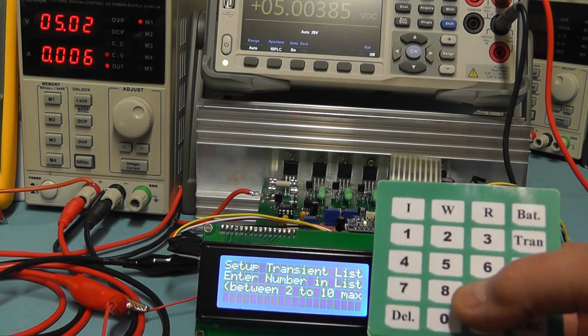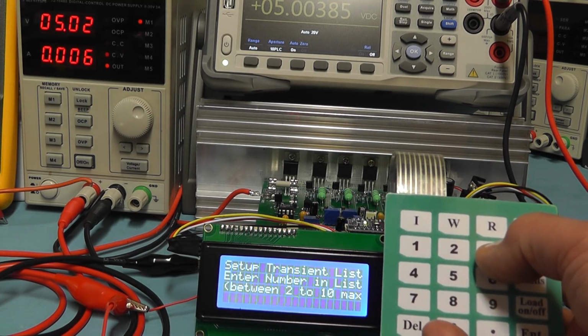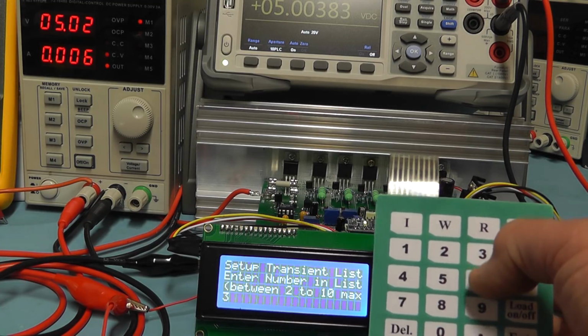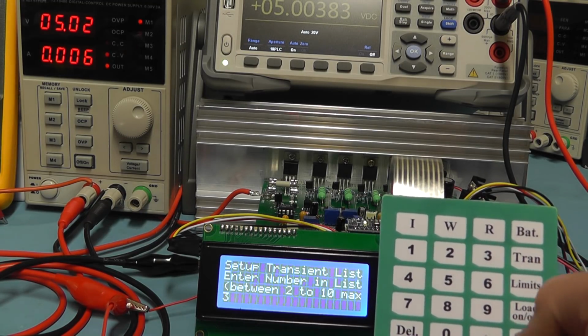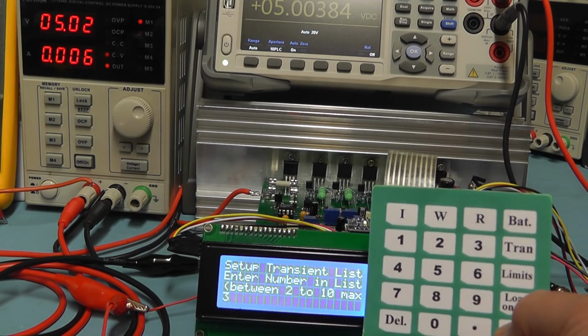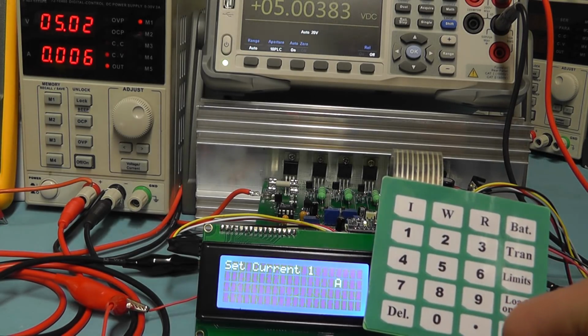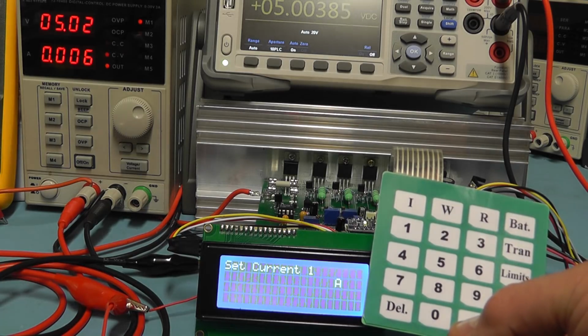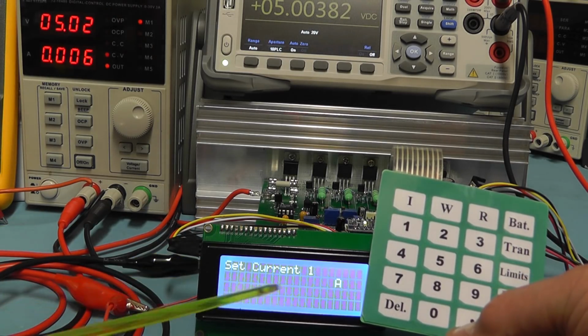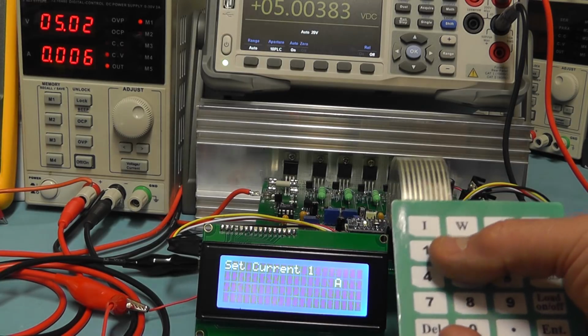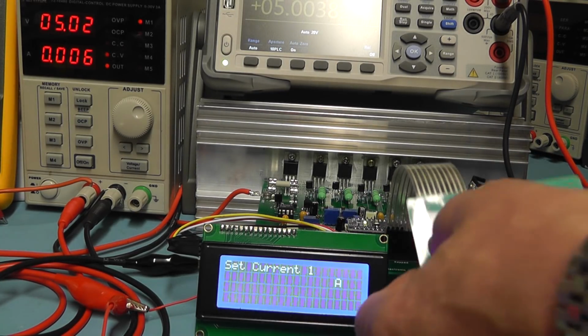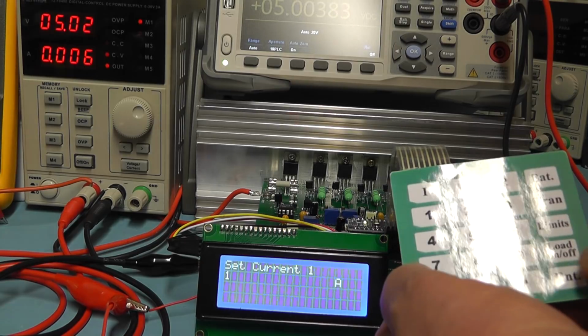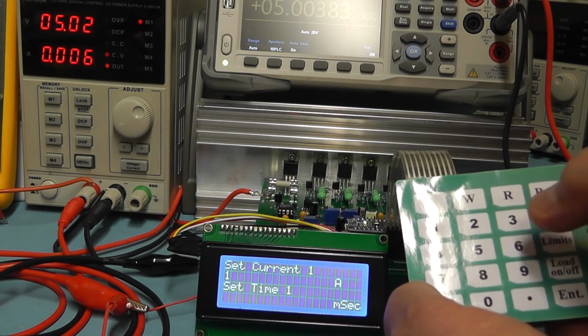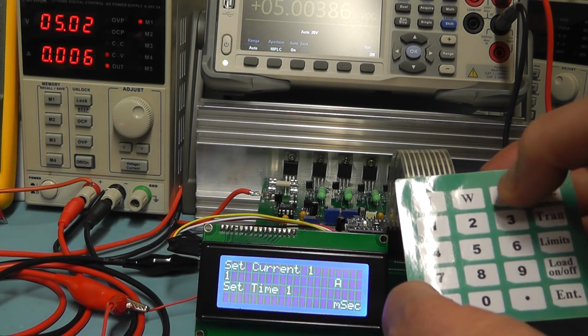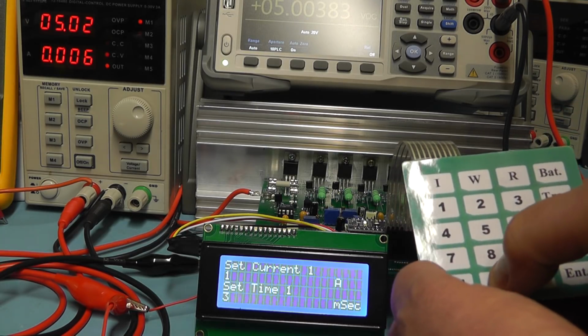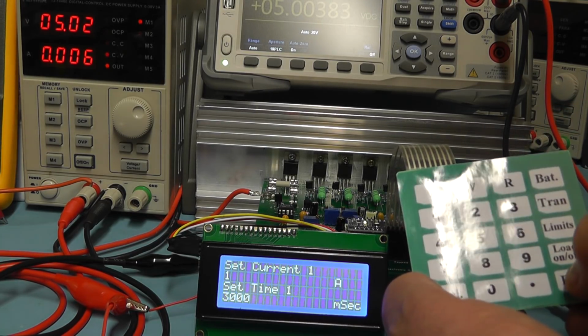So let me choose, just for this example, I want to say 3, so type in 3, it shows on the display, and then type enter. So we're going to have 3 different current and time settings. It comes up on the display, it says set current 1, so we're going to set the first current to say 1 amp and enter. We're going to set the time, say, to 3000 milliseconds, that's 3 seconds, enter.